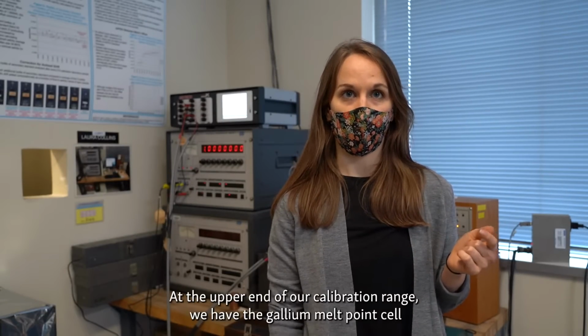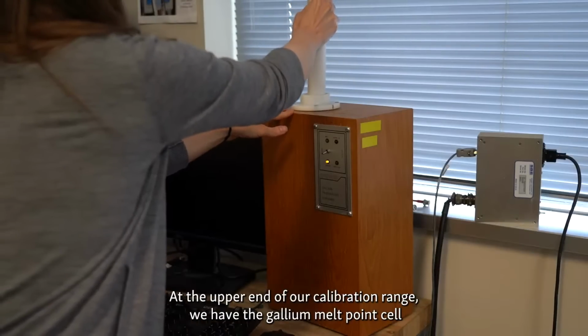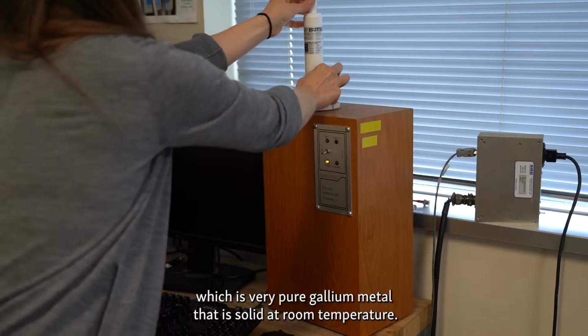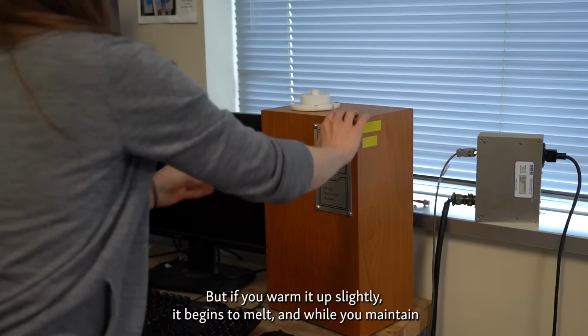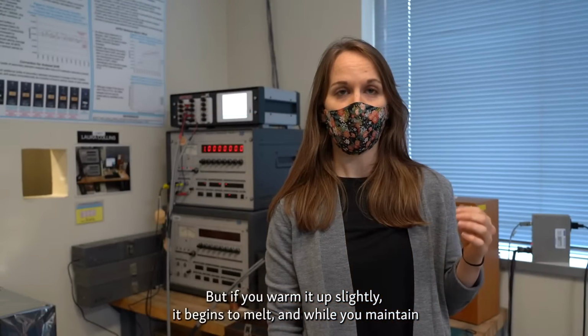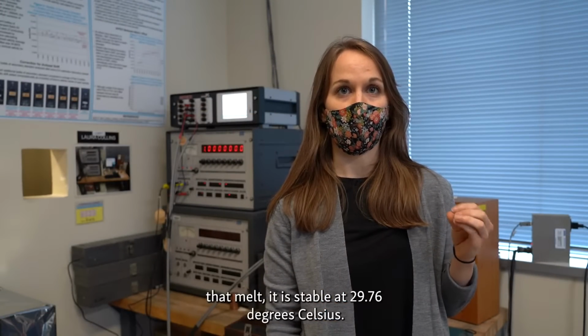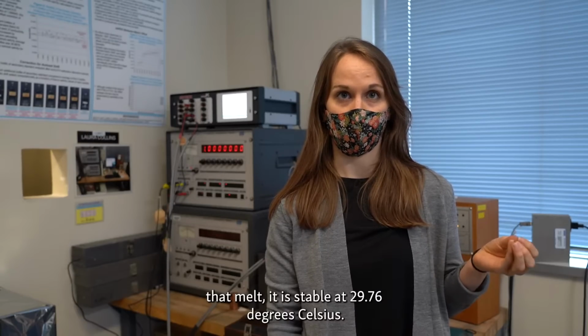At the upper end of our calibration range, we have the gallium melt point cell, which is very pure gallium metal that's solid at room temperature, but if you warm it up slightly, it begins to melt, and while you maintain that melt, it is stable at 29.76 degrees Celsius, so that's the upper end of our calibration range.